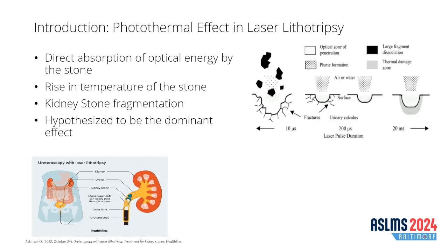The mechanism of action is primarily photothermal. In the past few decades, the clinical systems that have typically been used for this procedure are flash lamp pumped holmium YAG lasers, which have high peak power and operate in a very short pulse duration. Recently, however, diode pumped lasers have gained interest. The cartoon on the right shows the relative time domains between the two types of lasers, with the traditional clinical lasers being on the left of that cartoon and the more recent diode pumped lasers being in the medium to long pulse duration.